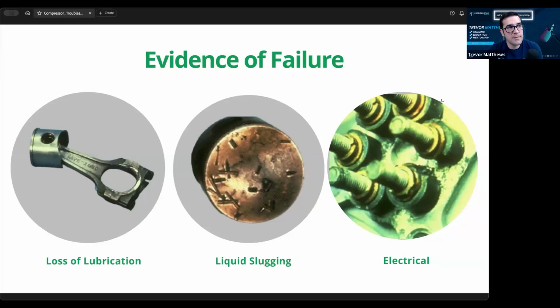And really all of it comes down to, at the end of the day, lubrication, right? All of those mechanical issues come back to lubrication because if you overheat, you're breaking down the oil. If you've got liquid coming back, it's washing out the oil. So all these things come back to lubrication. It's just we have these terms now that we use so you can identify if it was a liquid slug or if it was a washout.